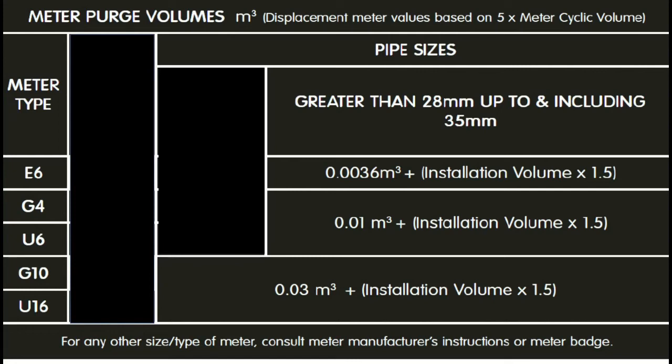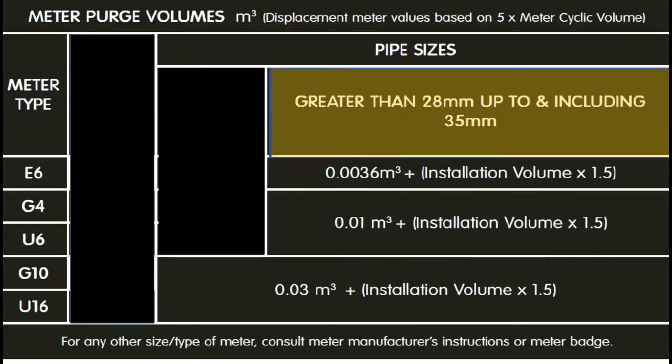However, if you've got pipework that's bigger than 28 millimeters, up as far as 35 millimeters, then you've got to use the second column. You simply do what it says in the box. If it's an E6 meter, you use the figure 0.0036 meters cubed, and then you add the installation volume, which is all the gas in the pipes plus 10% for fittings, and you times that little number by 1.5.